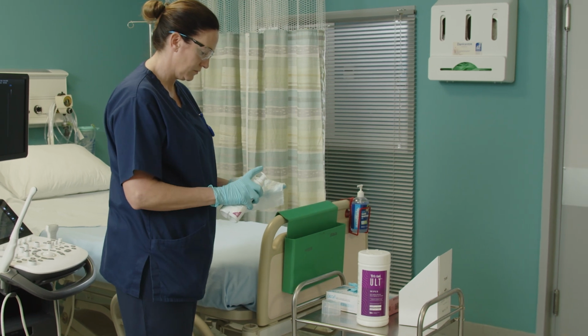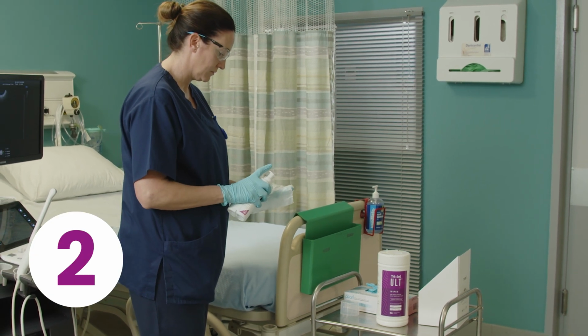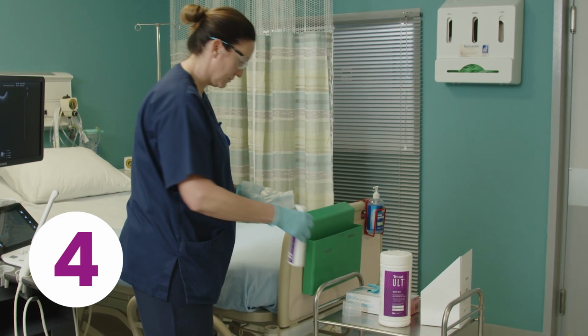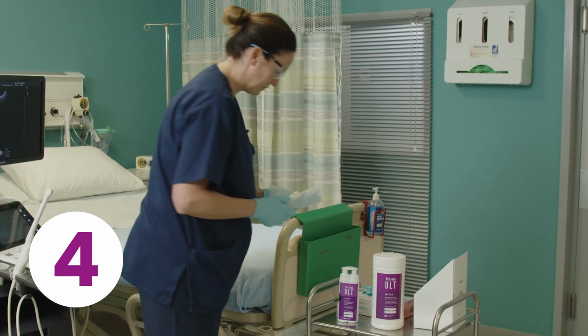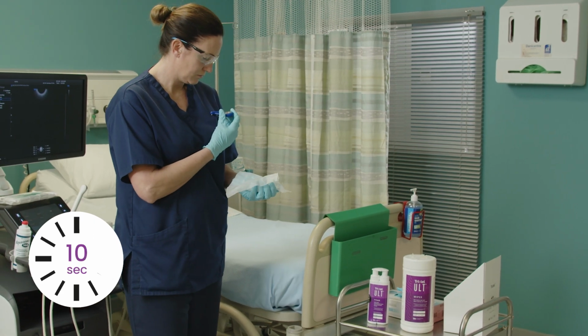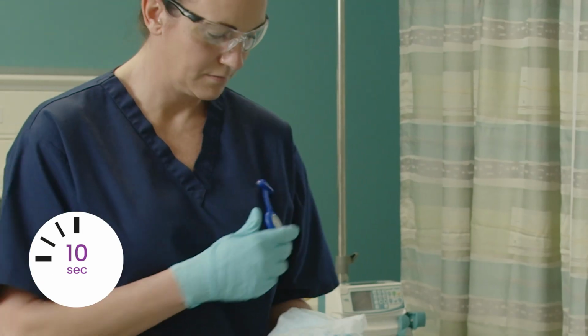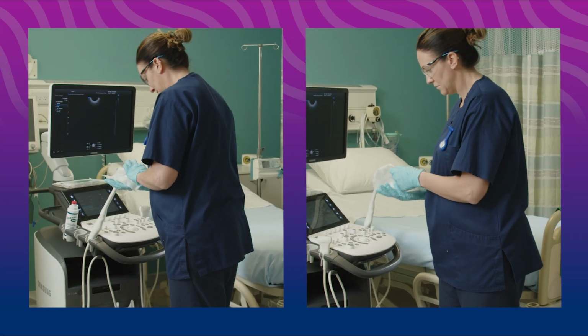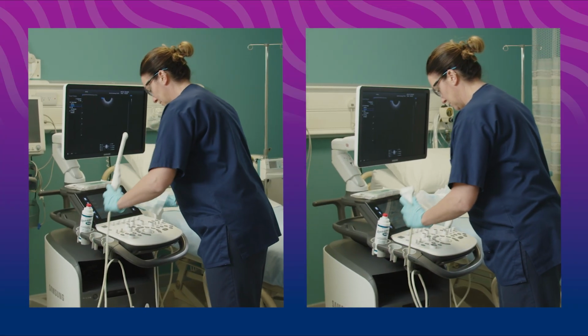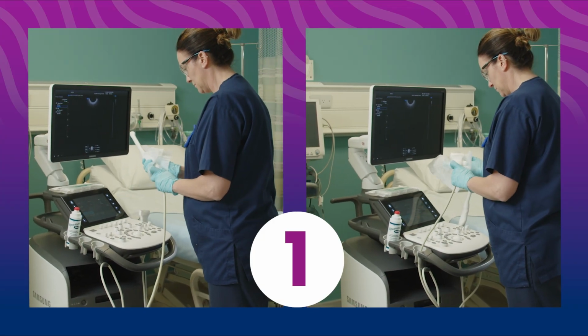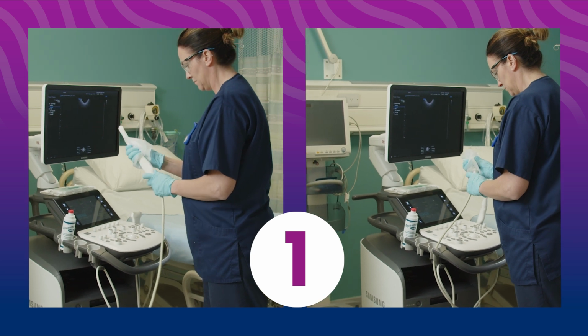To use Tristel ULT, begin by taking a Tristel ULT wipe in one hand and applying 4 doses of the Tristel ULT foam into the wipe. When the 4 doses have been dispensed, close your hand around the Tristel ULT wipe and wait 10 seconds. Use the Tristel ULT wipe to apply the foam in a massaging motion from one end of the device to the other 4 times.